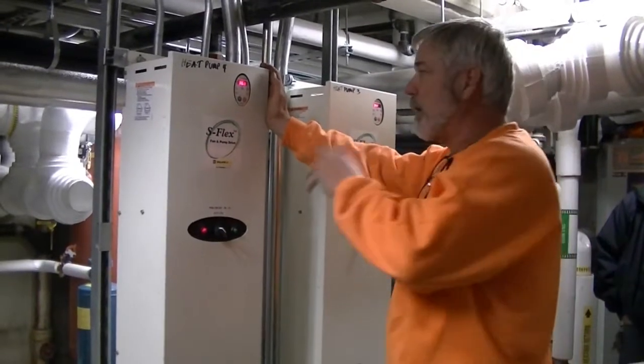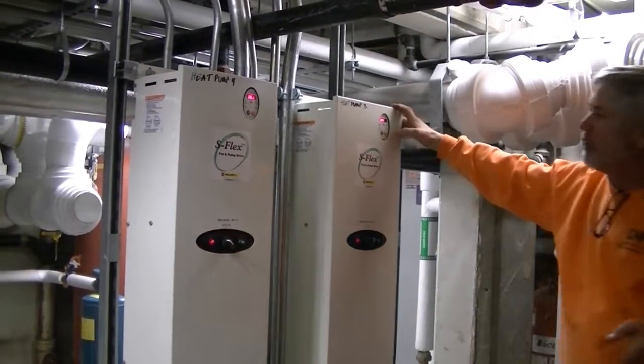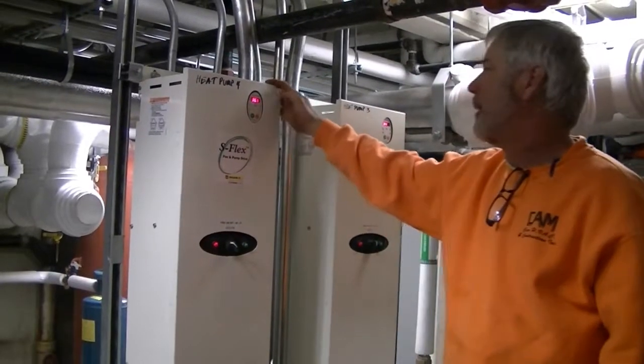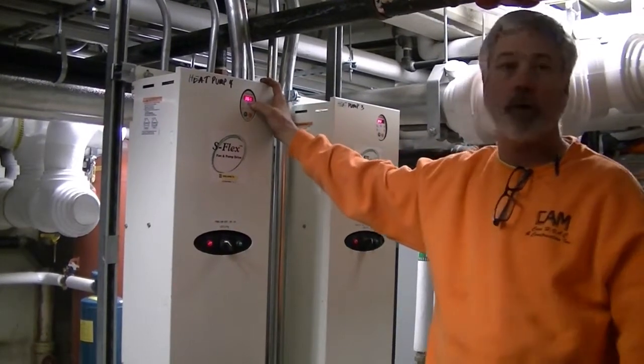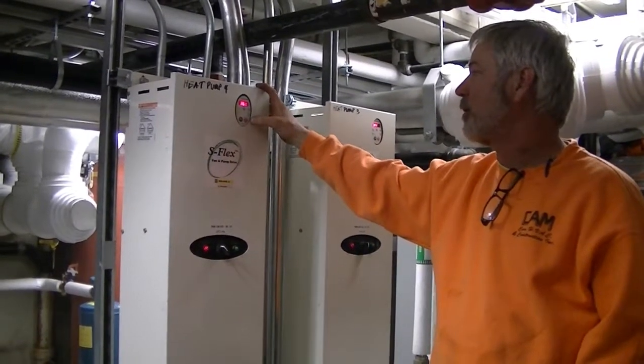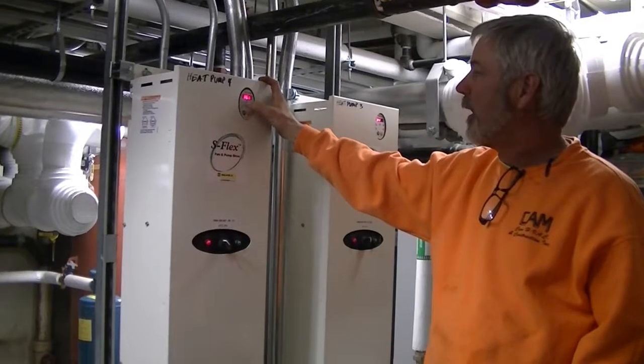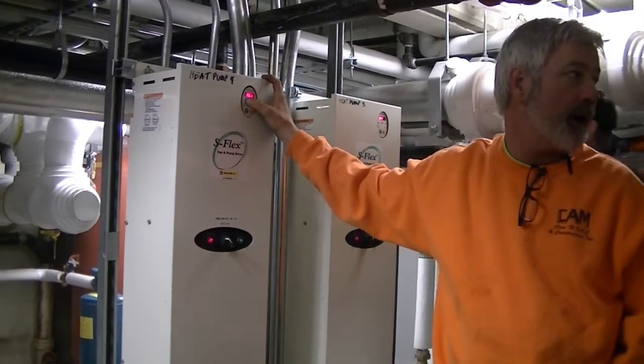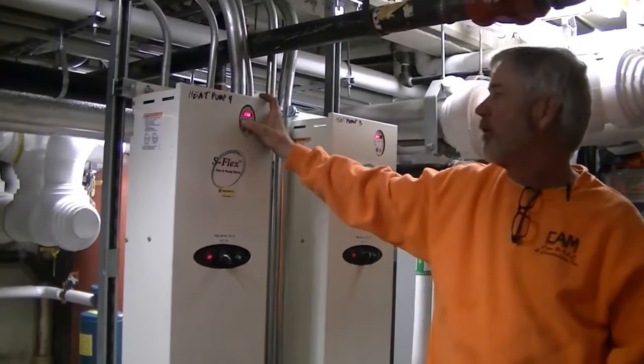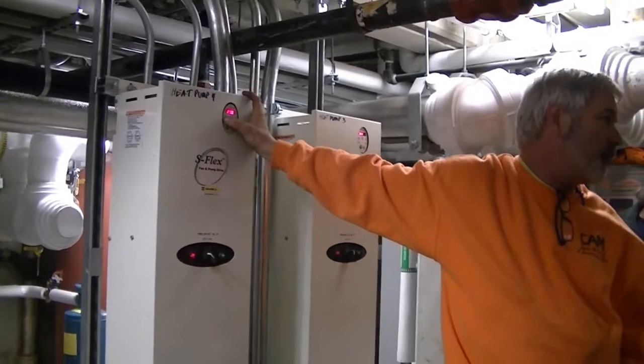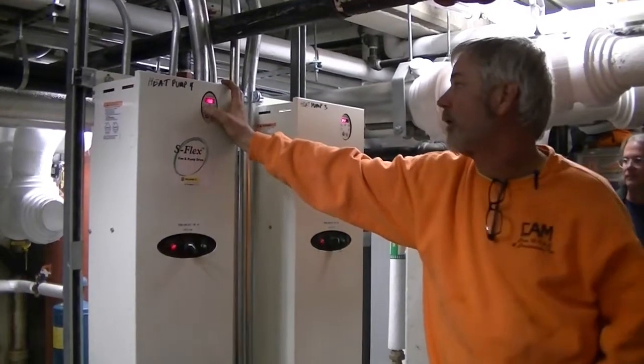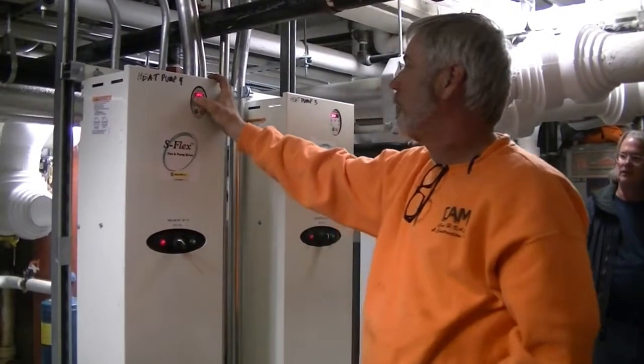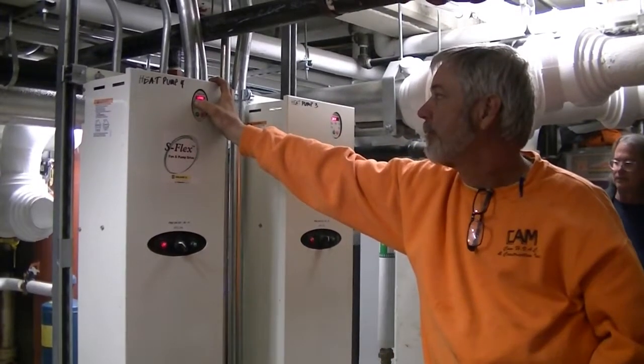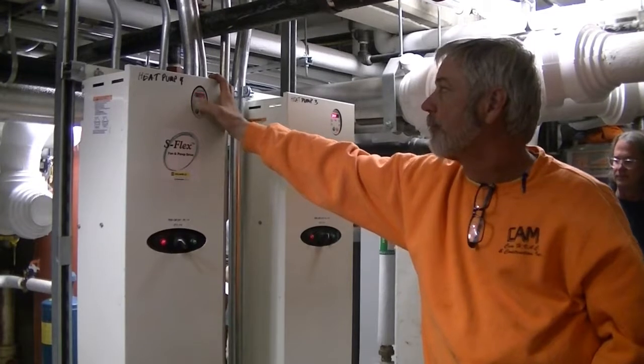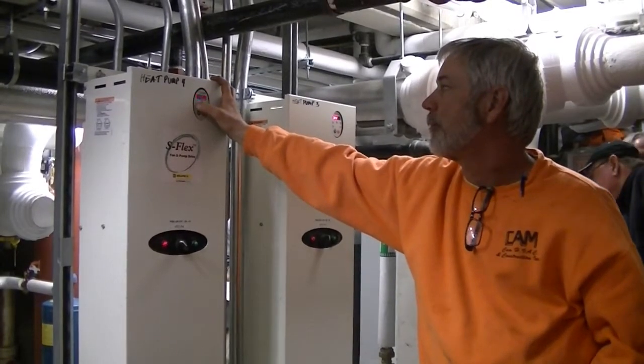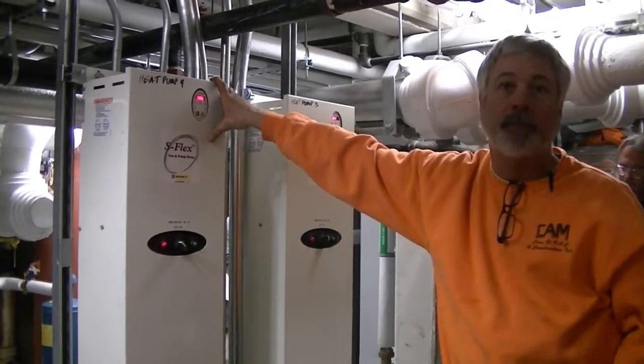If you want to run the pump on the drive but not through the control system, that can be done also. You put the drive in manual, which is a local remote button. The green indicator lights will come on, the run light will come on, and the green indicator light next to the up and down arrow will come on too. I can adjust the speed of this drive right now without the control system. You can hear the motor turning down. 15 hertz, that's your low limit. I'll put it back up to 36. You hear the drive come back up.